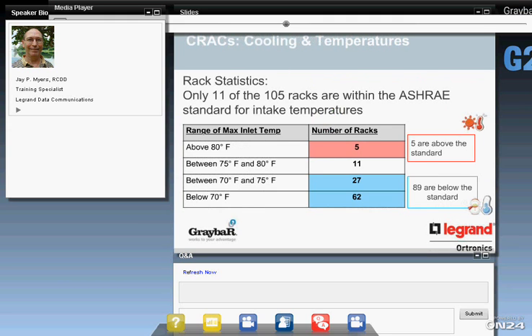Okay, so at our starting point, we have 5 racks above 80 degrees, above the recommendation of ASHRAE. That's too hot. That endangers the equipment. We have 11 racks that are in the proper range where we want them. And then we have 89 below that range, so they're cooler than they need to be. So they represent wasted money.